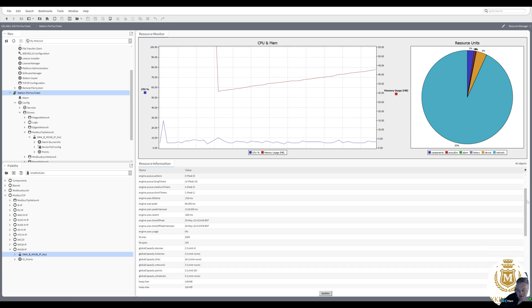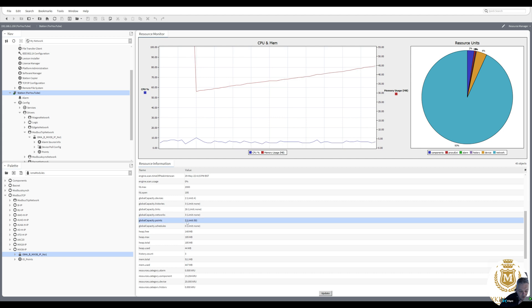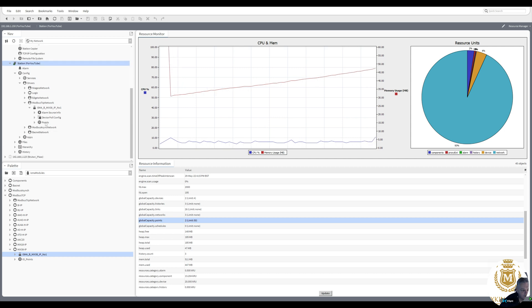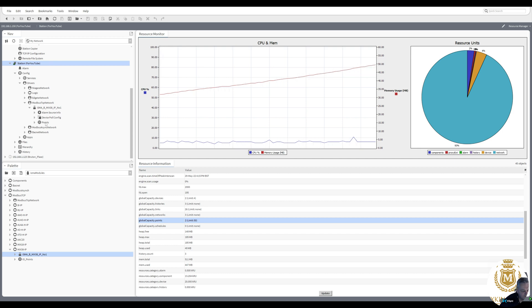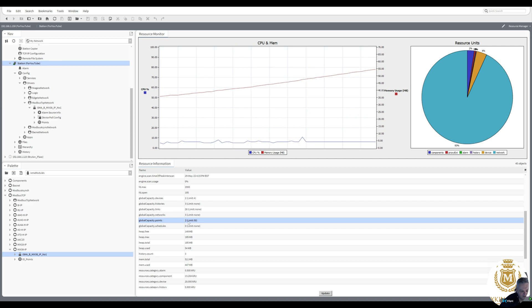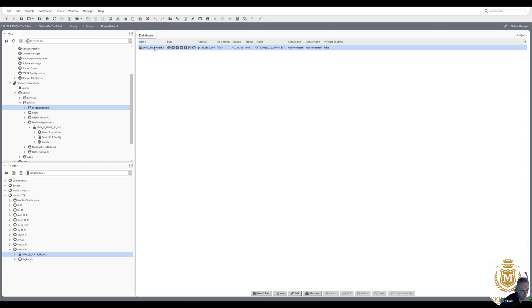If we look at the resources of this 50-point Jace, we're only using two points out of the 50, yet we know we've got 38 points available on the Mix as long as they are all digital inputs and digital outputs. If we start adding analog outputs or universal inputs, we would increase the global capacity point count.